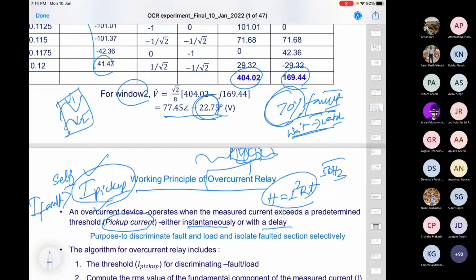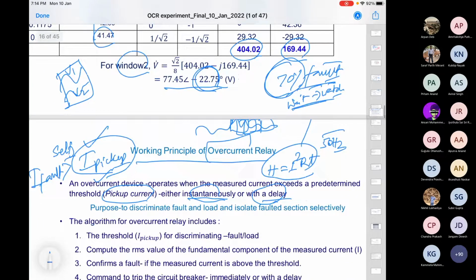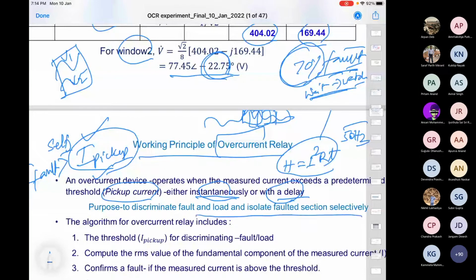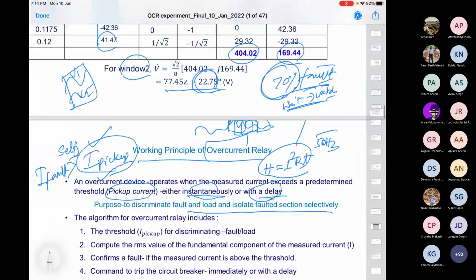Who will allow? The system will allow. In a distribution system, because the fault current magnitude is small compared to the high voltage system, I can allow some time, which will not lead to damage or any stress to the system. So you can allow some time. That's why the question: can I use a little bit of delay, or is it instantaneous? Furthermore, this time frame is also a discriminating factor. We'll see later on. The purpose is to discriminate fault and load and isolate the faulted section selectively. Is it a permanent fault or not? Most of the faults are not permanent. 30% of faults are permanent.